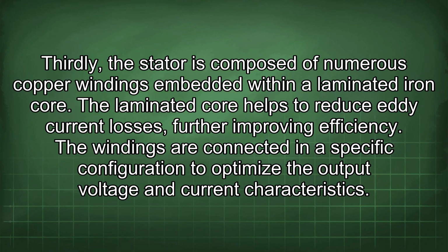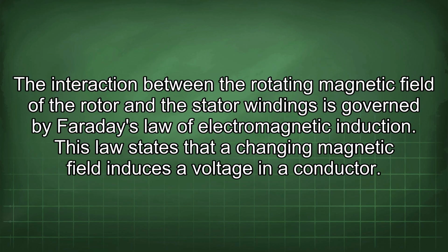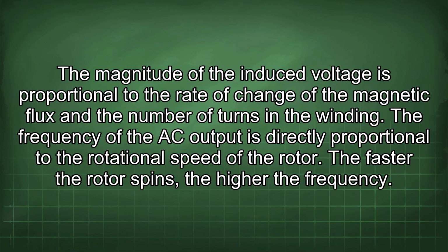Thirdly, the stator is composed of numerous copper windings embedded within a laminated iron core. The laminated core helps to reduce eddy current losses, further improving efficiency. The windings are connected in a specific configuration to optimize the output voltage and current characteristics. The interaction between the rotating magnetic field of the rotor and the stator windings is governed by Faraday's law of electromagnetic induction. This law states that a changing magnetic field induces a voltage in a conductor. The magnitude of the induced voltage is proportional to the rate of change of the magnetic flux and the number of turns in the winding.